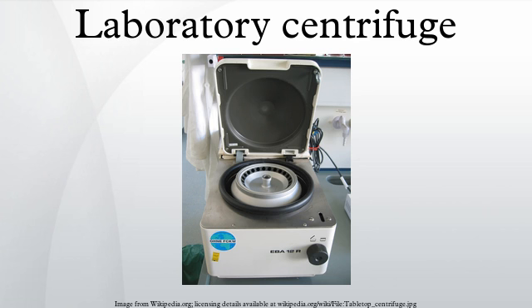To reduce the risk of rotor failures, centrifuge manufacturers specify operating and maintenance procedures to ensure that rotors are regularly inspected and removed from service or derated when they are past their expected lifetime. Another potential hazard is the aerosolization of hazardous samples during centrifugation. To prevent contamination of the laboratory, rotor lids with special aerosol-tight gaskets are available.